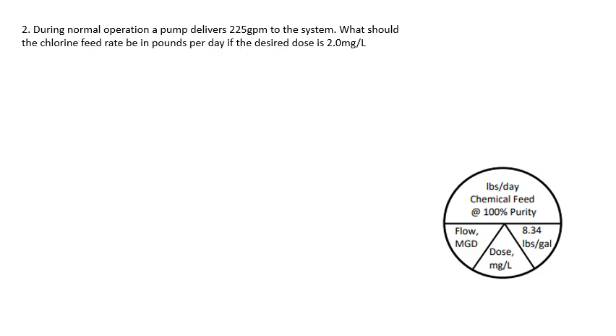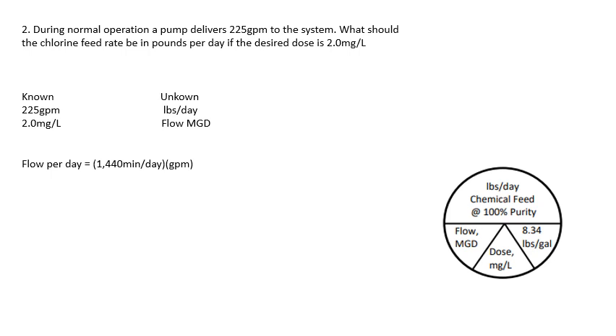During normal operation, a pump delivers 225 gallons per minute to the system. What should the chlorine feed rate be in pounds per day at the desired dose of 2.0 milligrams per liter? Start with your knowns and unknowns. We have 225 gallons per minute and a dose of 2.0 milligrams per liter. What we don't know is the pounds per day or the flow in million gallons per day. To solve for the flow per day: 1,440 minutes in a day times 225 gallons per minute gives a flow of 324,000 gallons per day.